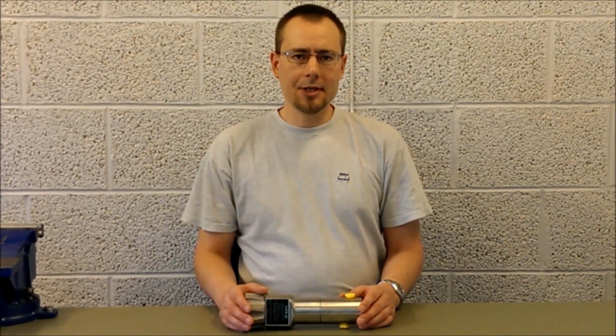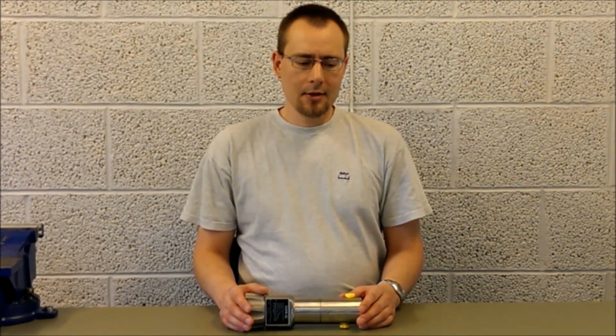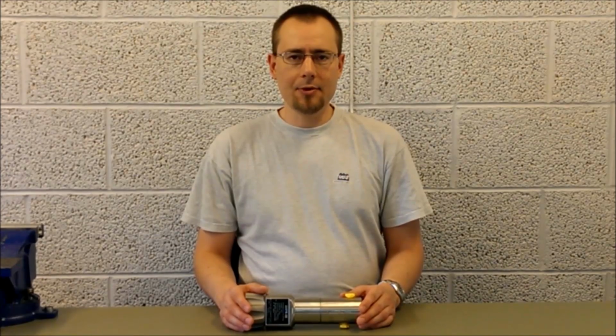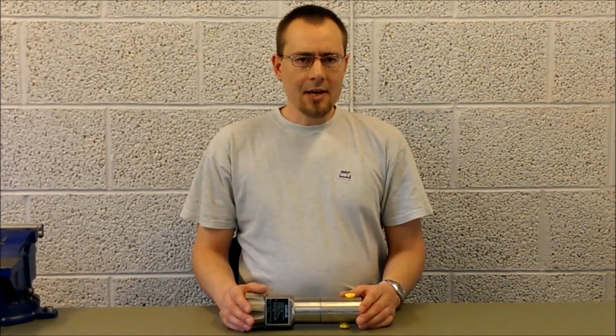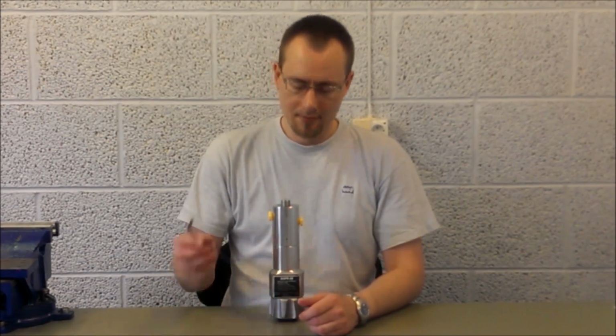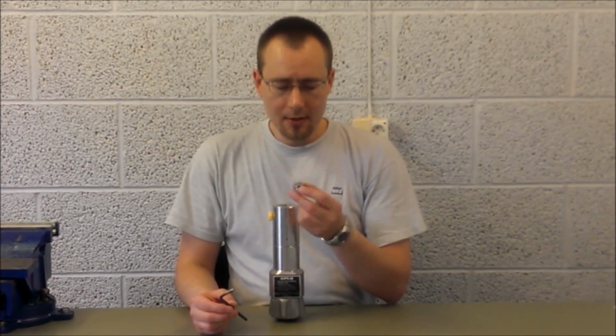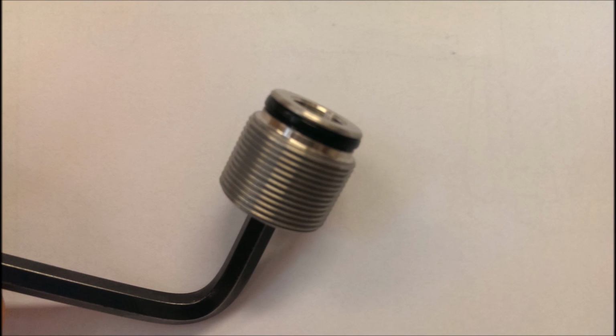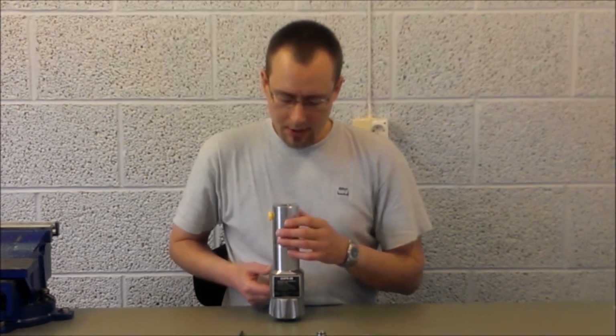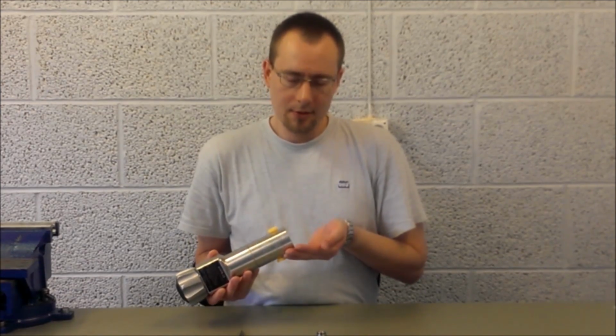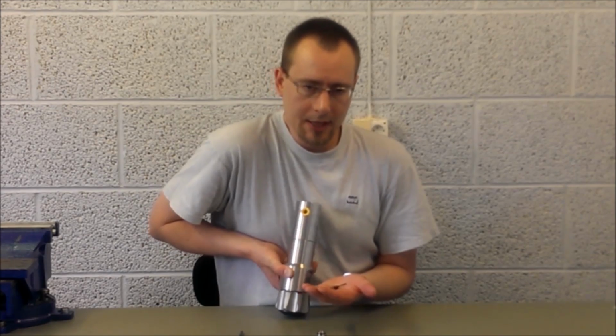Now we will go through the procedure of change of the inlet valve. First, make sure that the system is depressurized and that valves upstream and downstream of the regulator are closed. Pay attention to special local procedures. The cap has been pre-greased with threading paste. Inspect the O-ring for damages. Now, when you have removed the cap, the spring of the inlet valve and the valve body is loose. Turn it with a hand to receive both the spring and the valve body.